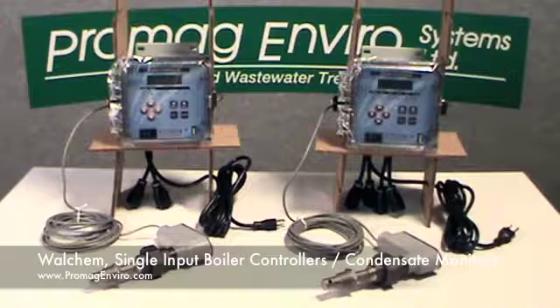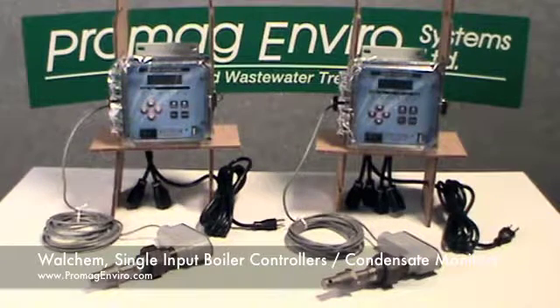The electrode material is 3/16 inch stainless steel and PEEK. The conductivity range is 0 to 10,000 µS per centimeter. Each unit comes standard with a convenient USB port, which can be used for data logs, event or relay and reset logs, and user configuration file import or export.